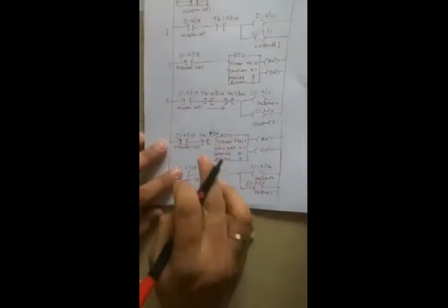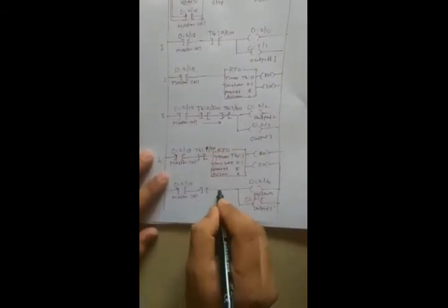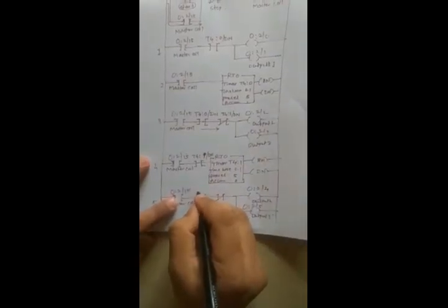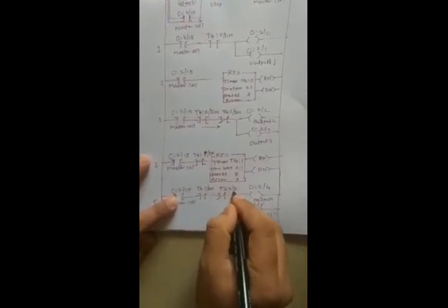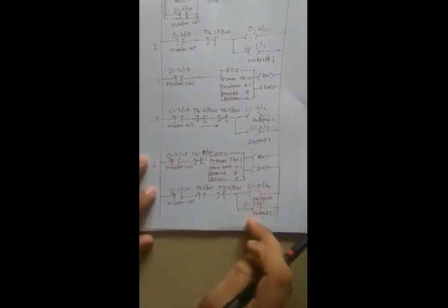Okay, similar to the earlier rung 3, you have to add the done bits respectively in the fifth rung. So here the done bits will be the T4:1 done bit and the T4:2 done bit. Whenever the next timer is executed and its done bit is enabled, then these lights will become off. These lights will become on and will remain on until the done bit of the timer 1.